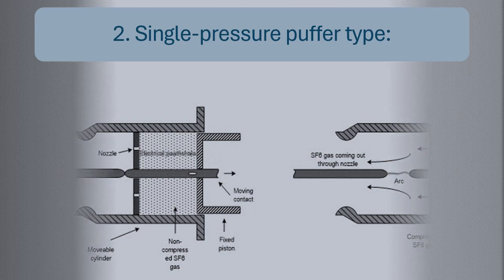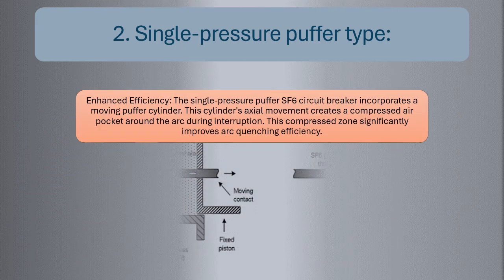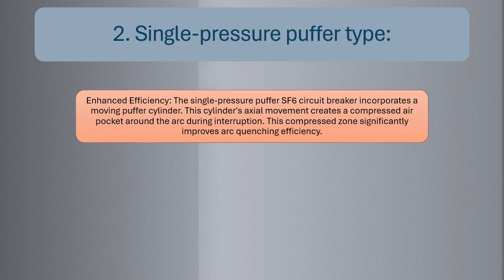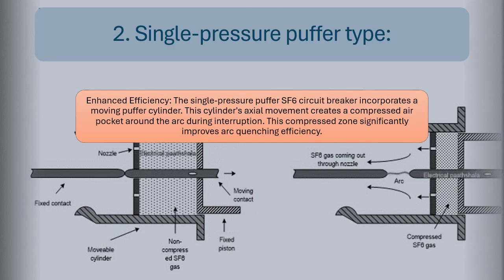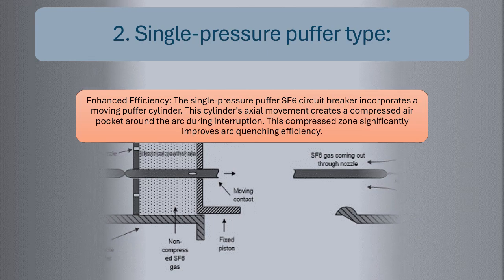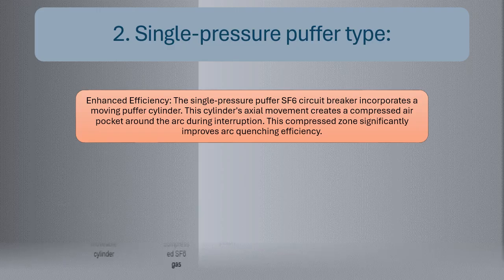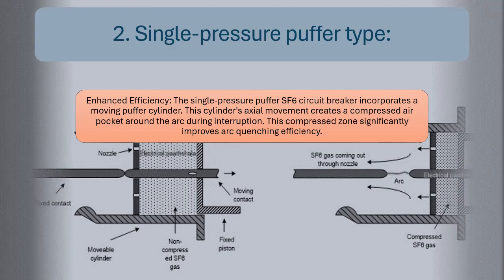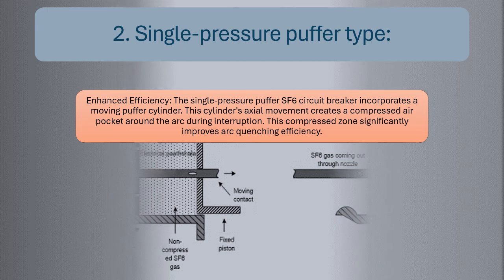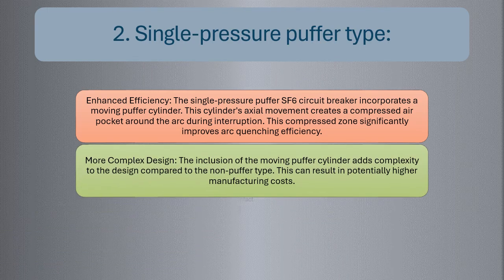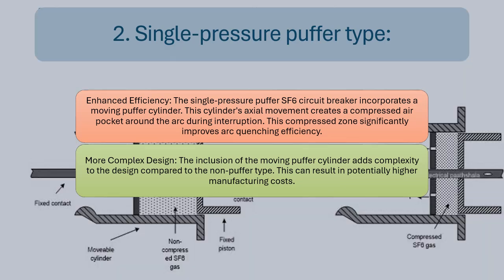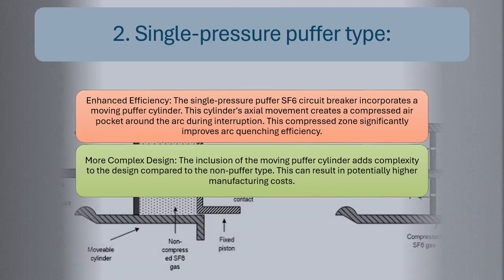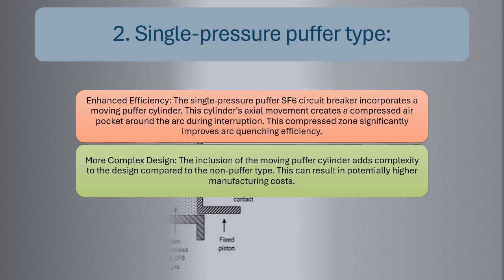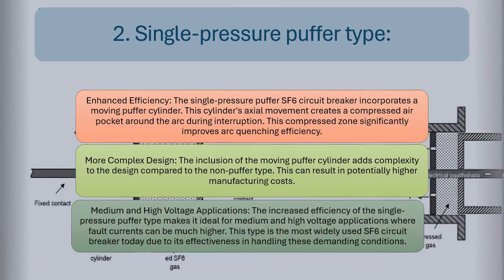Second, the single-pressure puffer type, offering enhanced efficiency. It incorporates a moving puffer cylinder. This cylinder's axial movement creates a compressed gas pocket around the arc during interruption, significantly improving arc quenching efficiency. However, the inclusion of the moving puffer cylinder adds complexity to the design compared to the non-puffer type, which can result in potentially higher manufacturing costs.